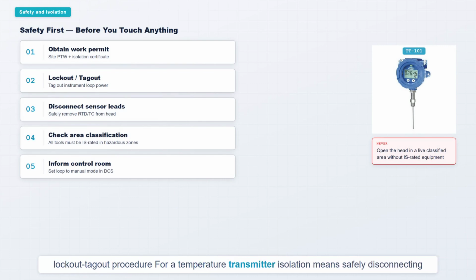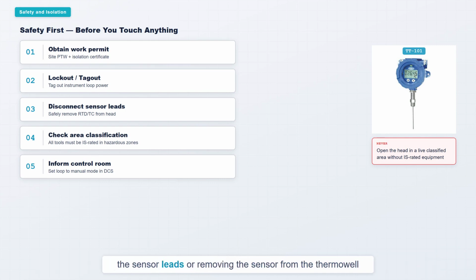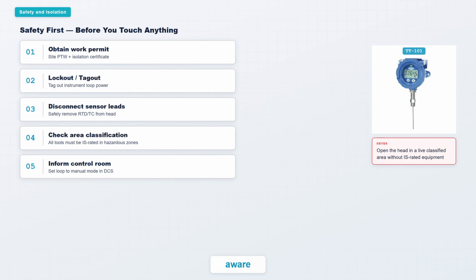Before starting, obtain your work permit and follow the site lockout-tagout procedure. For a temperature transmitter, isolation means safely disconnecting the sensor leads or removing the sensor from the thermowell. Check the area classification. In a hazardous zone, verify that all instruments and tools are intrinsically safe rated. Never open a transmitter head in a live classified area without the correct equipment. Confirm with the control room that the transmitter loop is in manual mode and the DCS operator is aware.